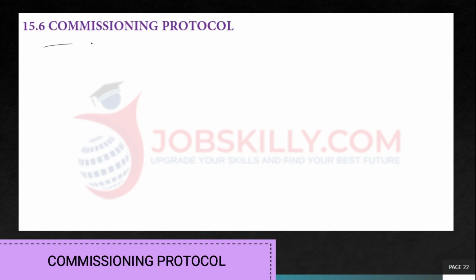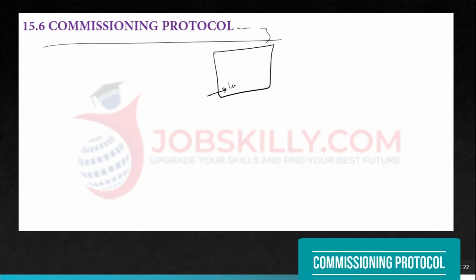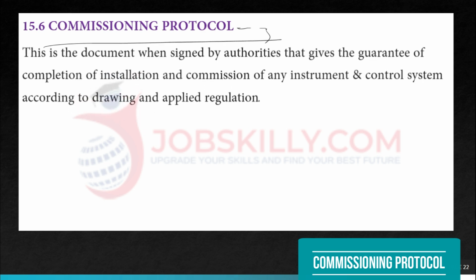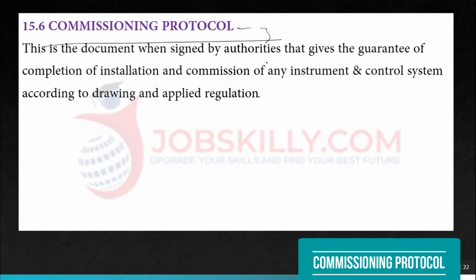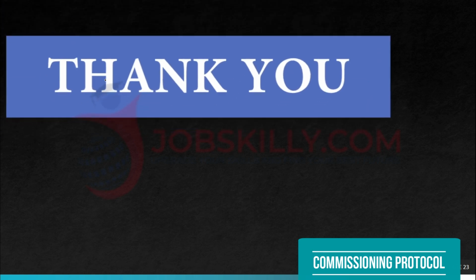What is the commissioning protocol? This is very important when you go for the C&I erection. Here, this is a document that is duly signed by the customer and vendor. This is the document which, when signed by authorities, gives the guarantee of completion of installation and commissioning of any instrument and control system according to the drawing and applicable regulations. So when this document has been signed, it will be the proof that our instrument has been commissioned as per the drawing and as per the applicable regulations. So this is a very important document. Thank you.